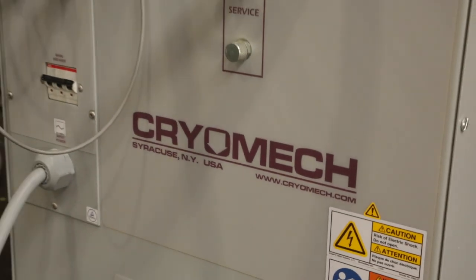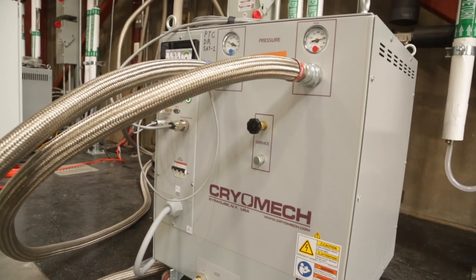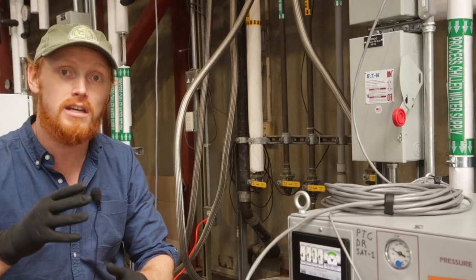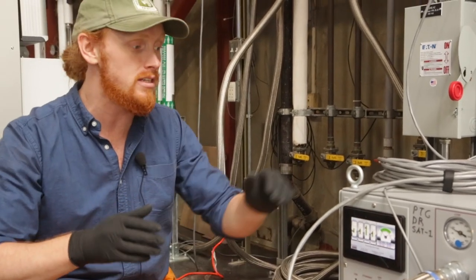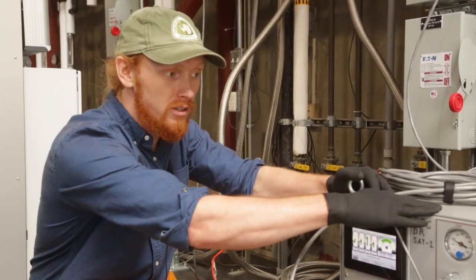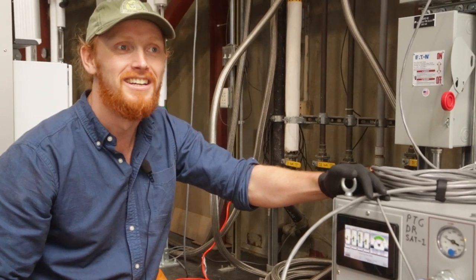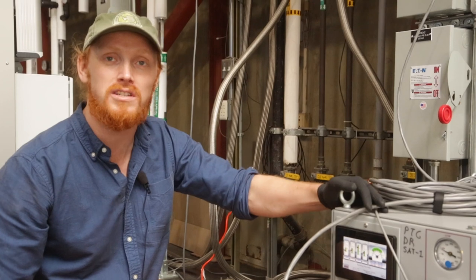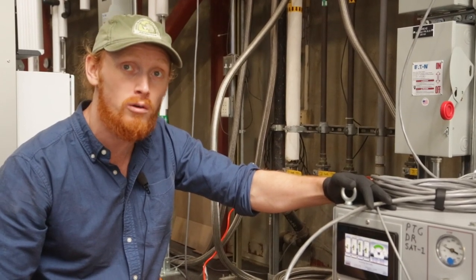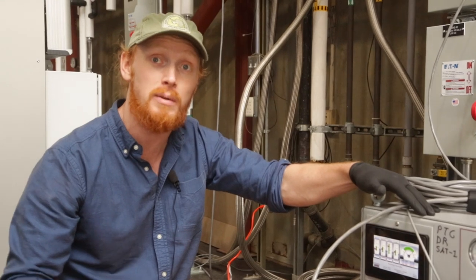This right here is a compressor that does a lot of the workhorse work. The pulse tube is a separate component from the BlueFors dilution refrigerator, which cools down to a 30 and 40 Kelvin stage and about a 3 or 4 Kelvin stage. It does that using gradients in helium pressure backed by this compressor unit. It requires high voltage to run, uses a lot of power, and is one of the main drivers of our power requirements at the site — right now using somewhere between 10 and 14 kilowatts.